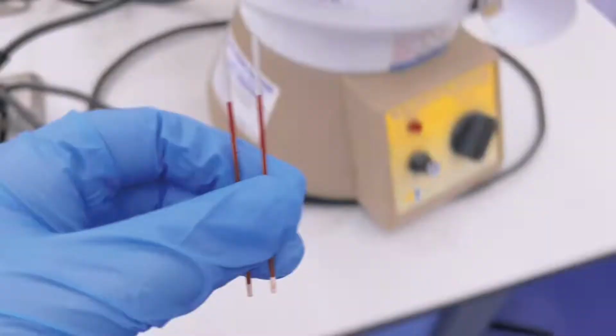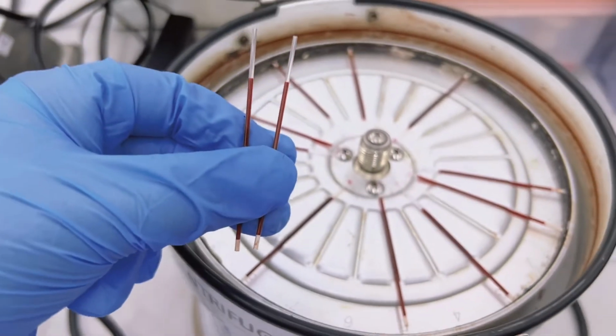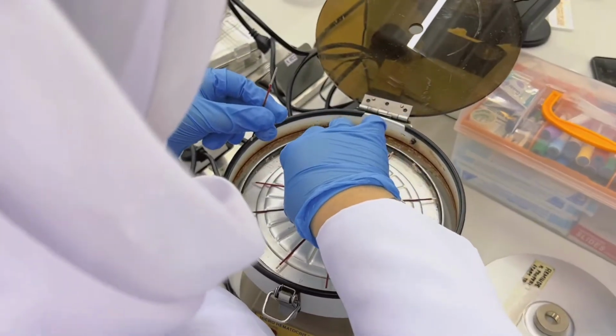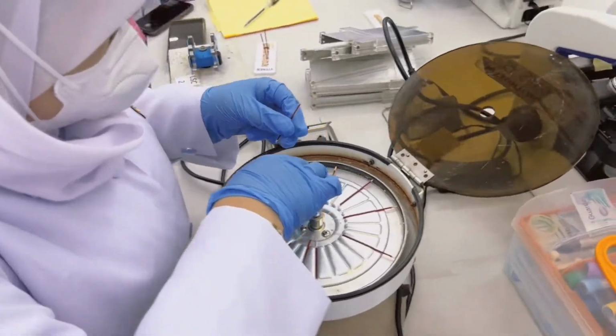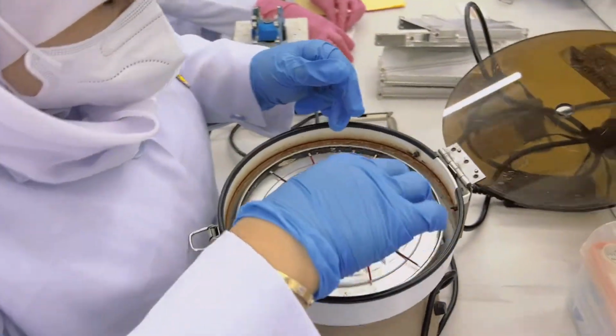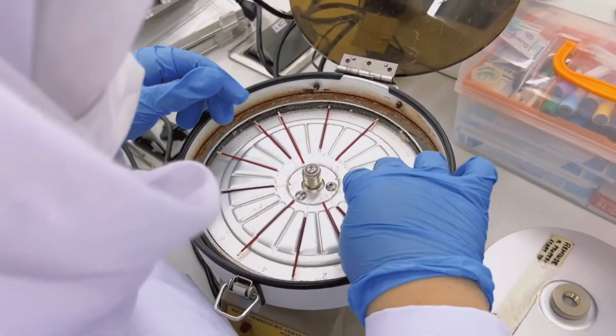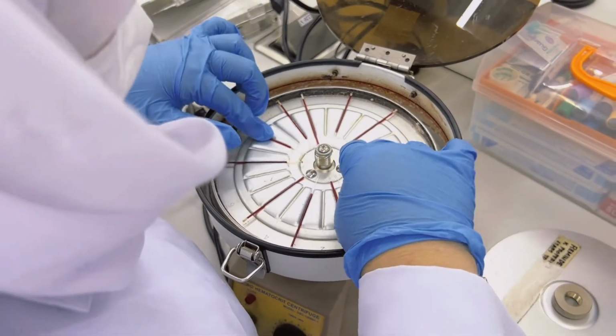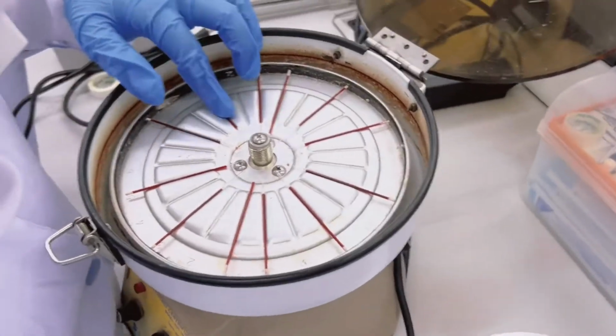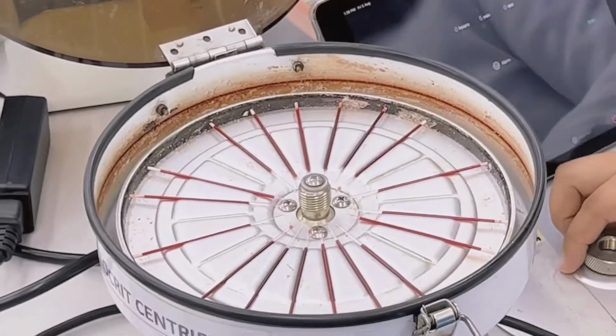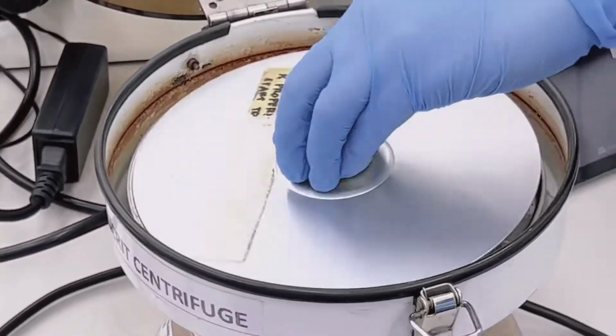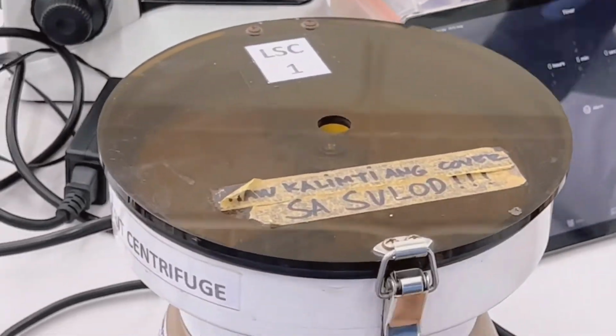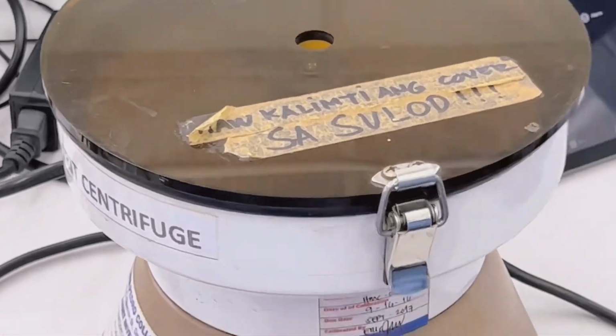Second part is the centrifugation of the sample. For centrifugation, the sealed tubes are placed in a radial groove of a special microhematocrit centrifuge. The sealed end of the tube is placed against the rubber gasket and the open end toward the center. Ballast the centrifuge by placing the tubes opposite each other. The lids of the centrifuge are secured and the tubes are centrifuged for 3 to 5 minutes.